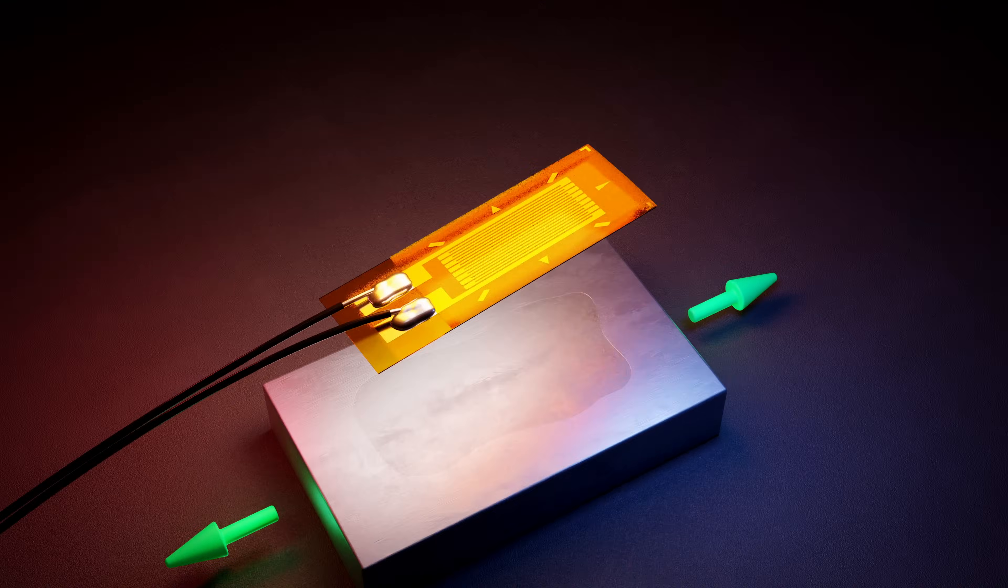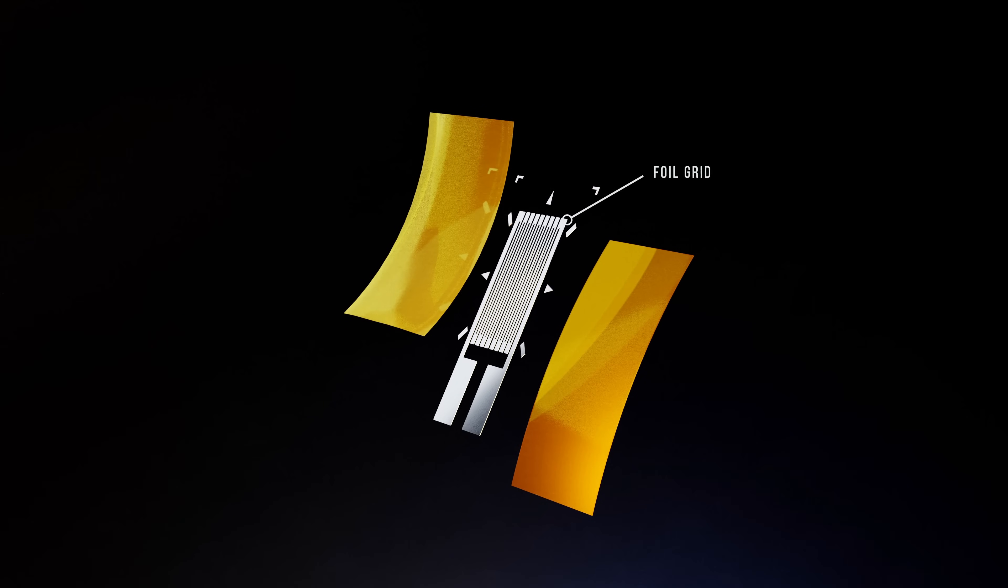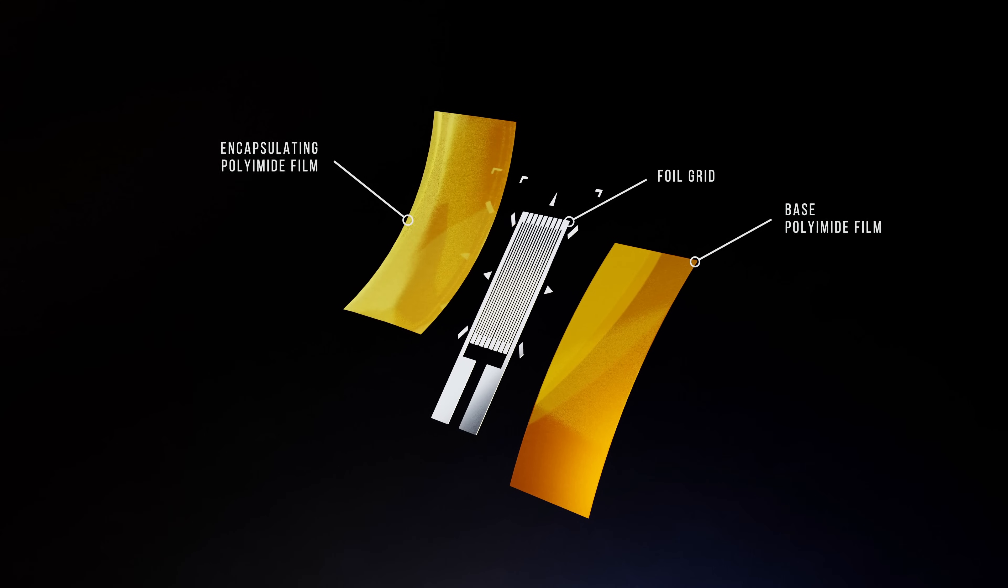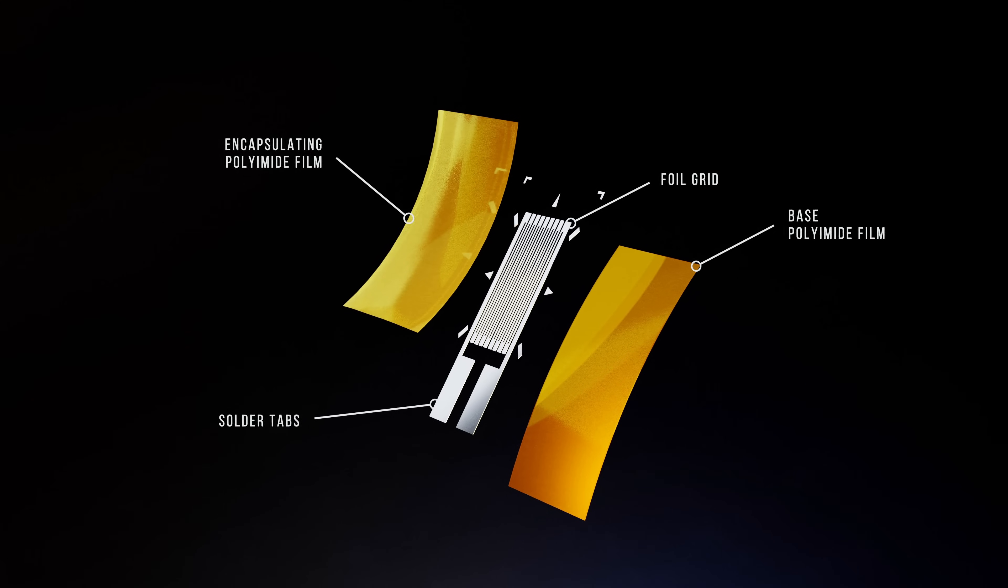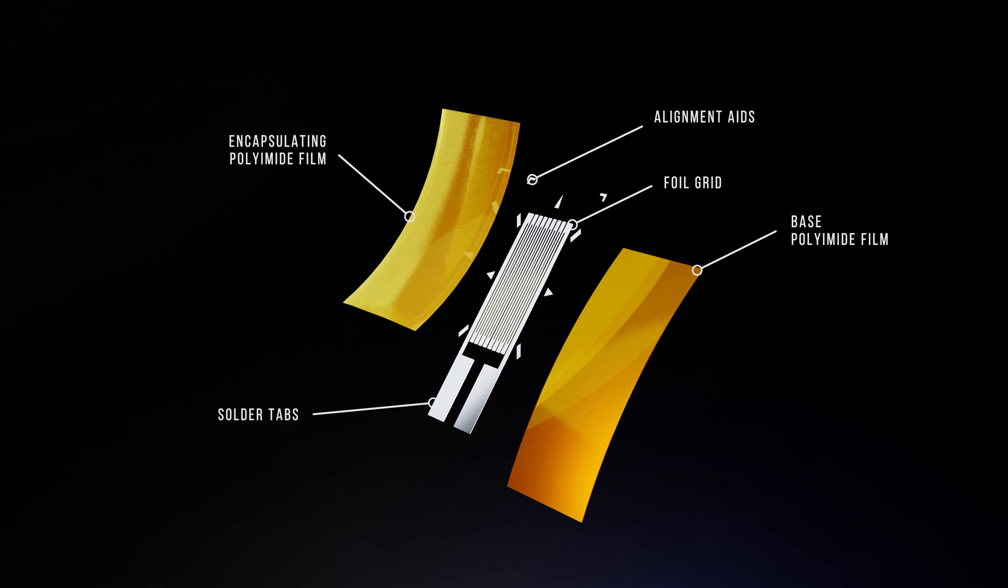The electrical resistance strain gauge is made of a conductive foil grid that's bonded to a very thin insulating plastic film. A separate film encapsulates and protects the foil grid. Solder tabs allow the measurement wiring to be soldered directly to the strain gauge, and markings on the foil help with alignment of the gauge during installation.